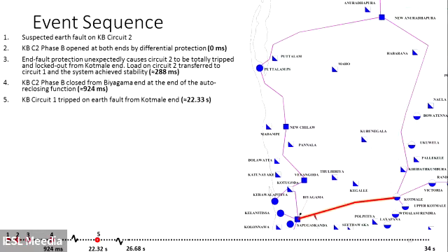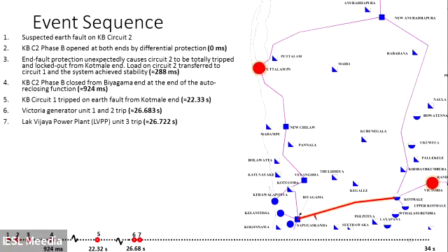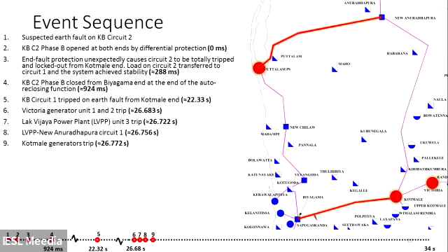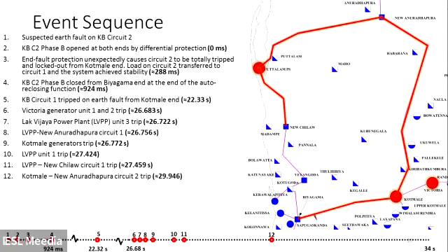Then after about 22.33 seconds, circuit 1 tripped. After that, as you may understand, there was a limited path for the power to flow. The generators started tripping: Victoria Generator Unit 1 and 2, then Lakvijaya Power Plant Unit 3. Unit 2 was not functioning at that time. Then the New Anuradhapura Circuit 1 to LVPP tripped, and then the Kothmale Generator tripped.